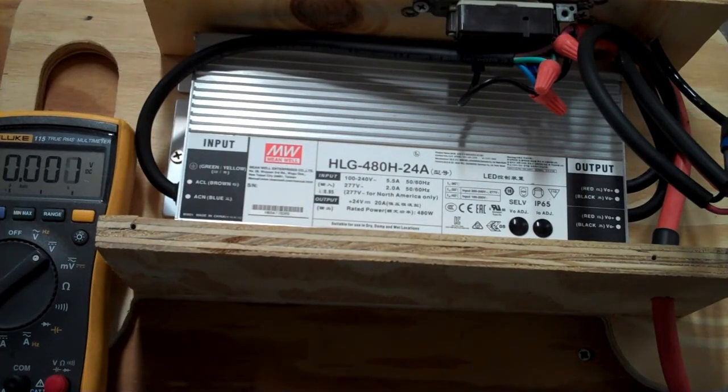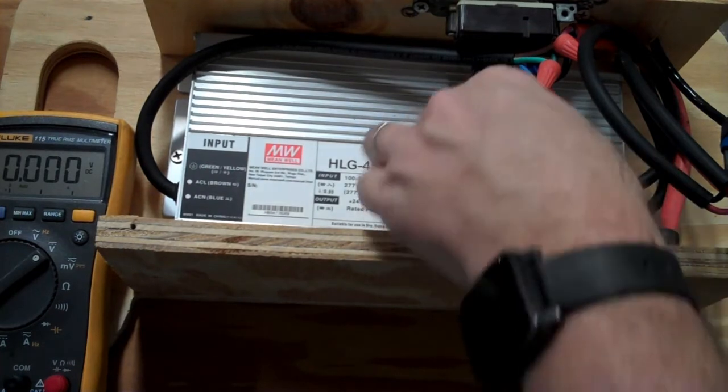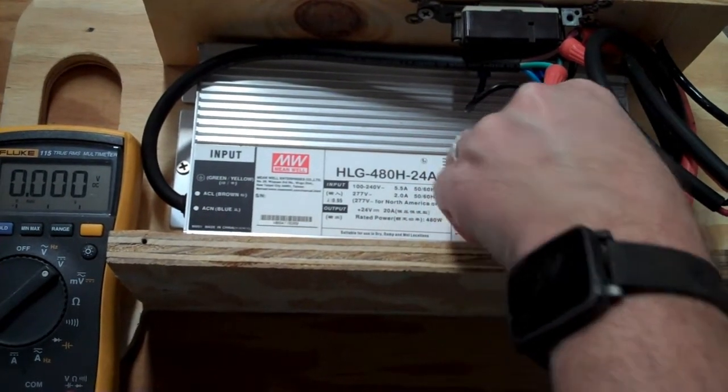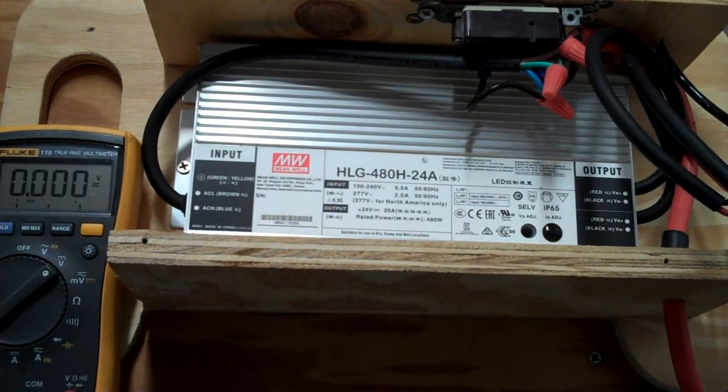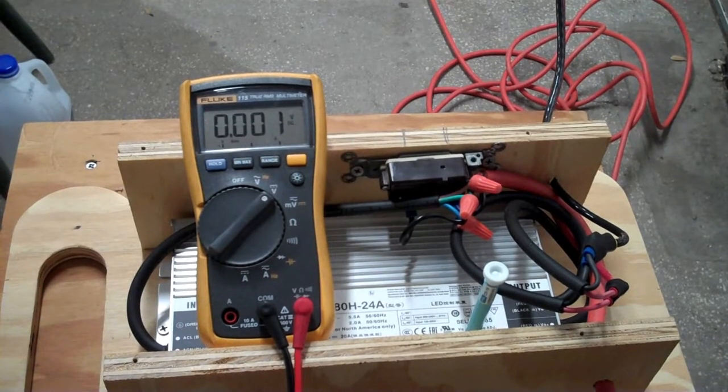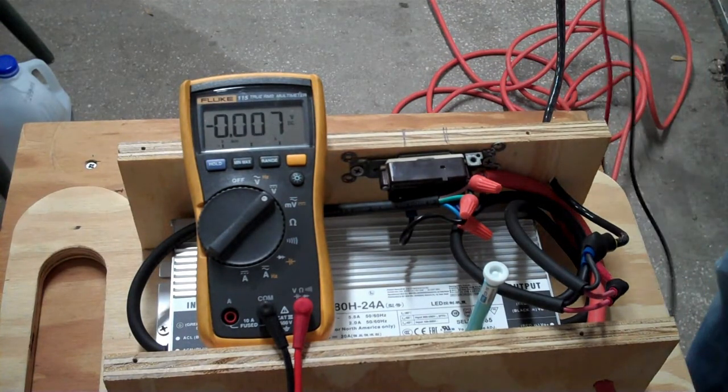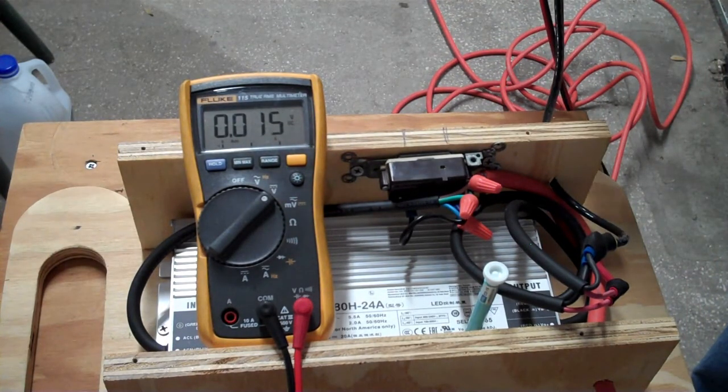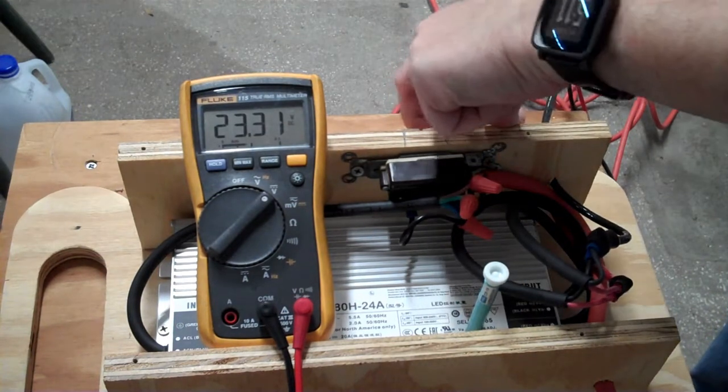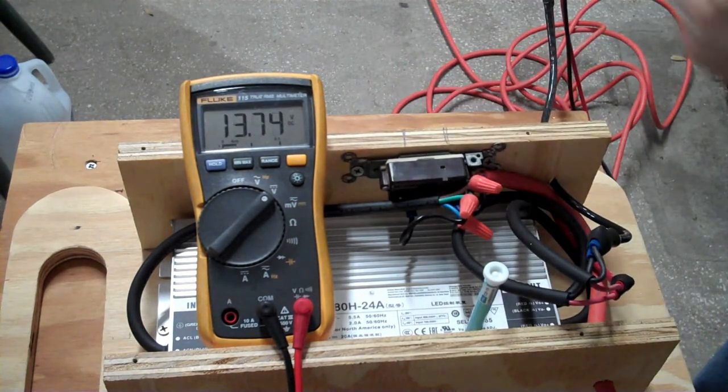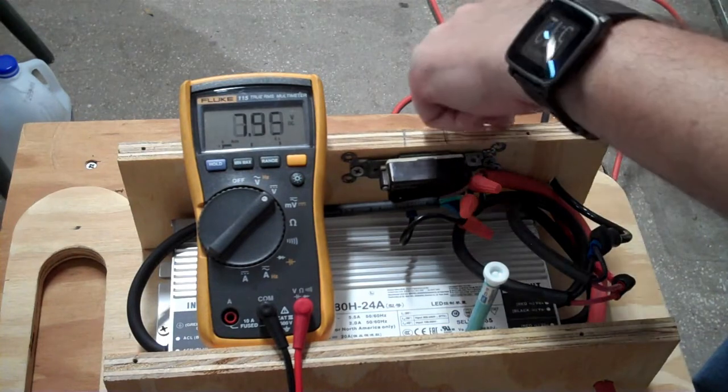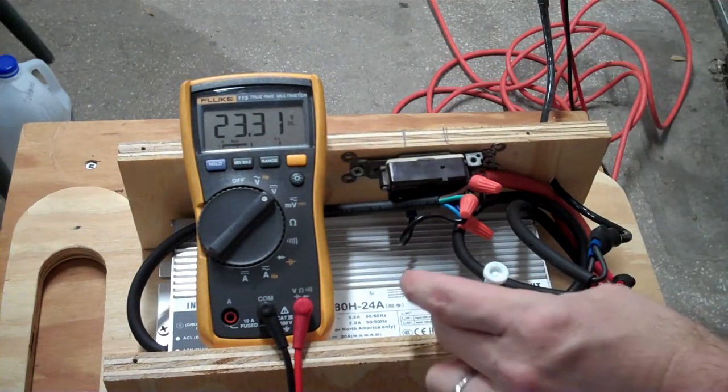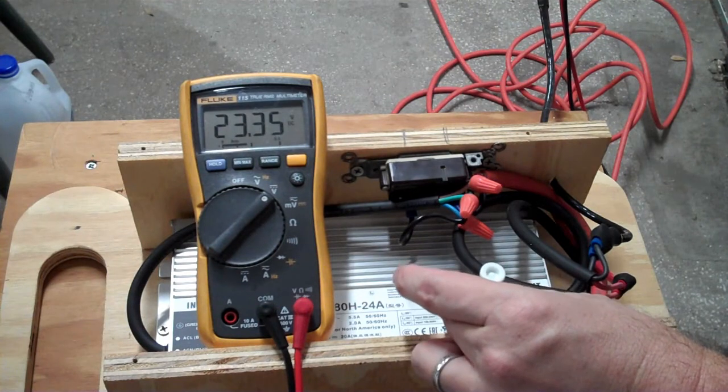So there's these two rubber plugs, voltage adjust, current adjust. I'm assuming the current is going to be set to maximum, so I don't need to adjust that, but I do need to bump the voltage up. Way down there in that hole is a potentiometer that you need to twist to adjust the voltage. So we are going to turn this guy on and adjust it to 24.6.